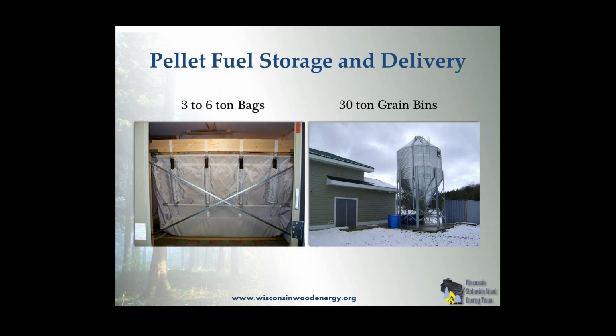A lot more flexibility with pellets on delivery. You can use flexible augers, so you can put in many different combinations and locations in order to get the pellets from the fuel storage to the boiler room. On the left is an installation we did in the basement of an old church up in New Hampshire. On the right, it's an outdoor pellet grain bin. That grain bin is probably in the range of $4,000 to $5,000 for the bin. Whole fuel delivery and storage system is probably well less than $10,000.